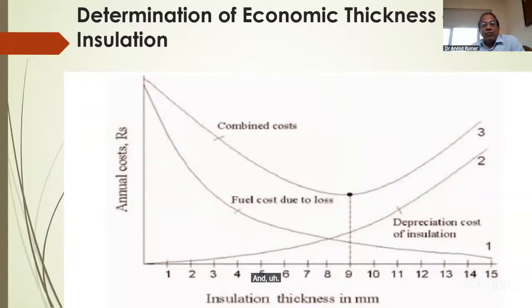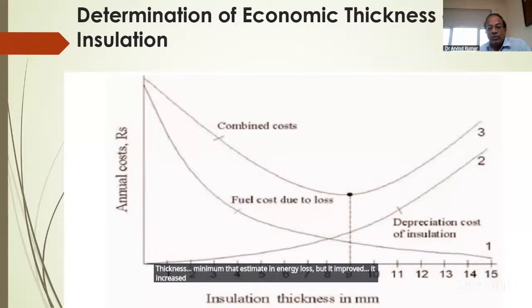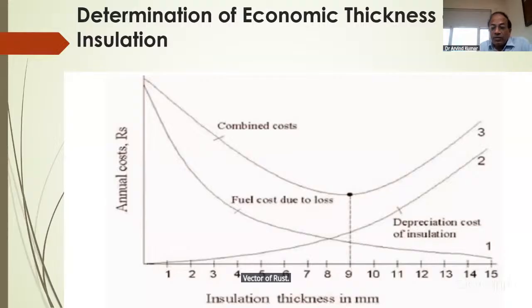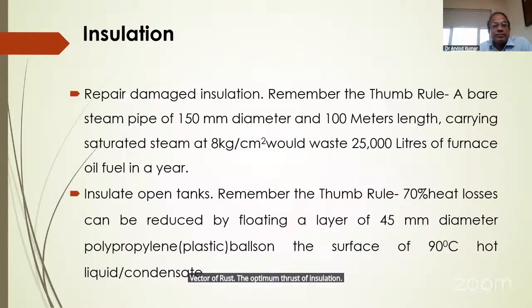We have to optimize the economic thickness of insulation. The more the insulation thickness, the less the steam and energy loss, but it increases the cost. So the optimum thickness we have to consider with the factor of cost. Repair damaged insulation. Remember the thumb rule: a bare steam pipe of 150 mm diameter and 100 meters length, carrying saturated steam at 8 kg per square centimeter, would waste 25,000 liters of furnace oil fuel in a year.